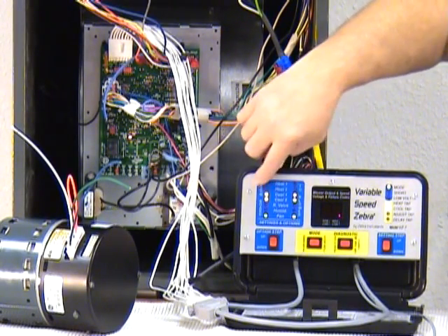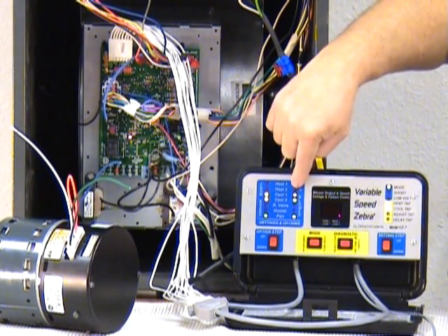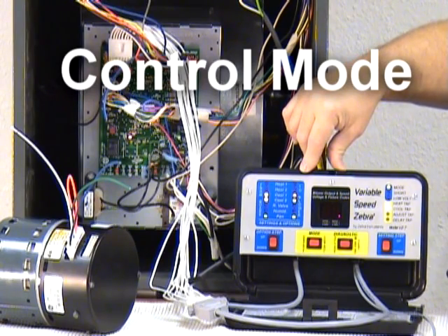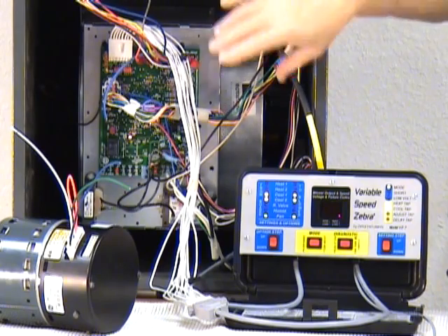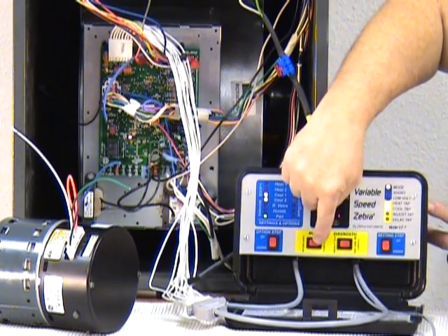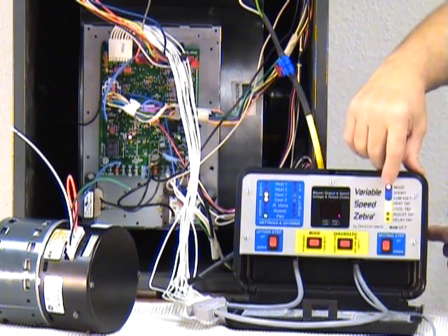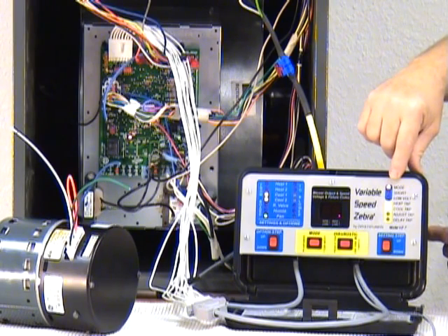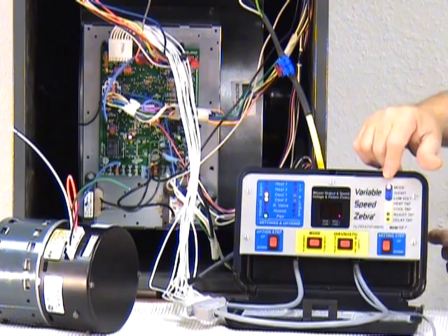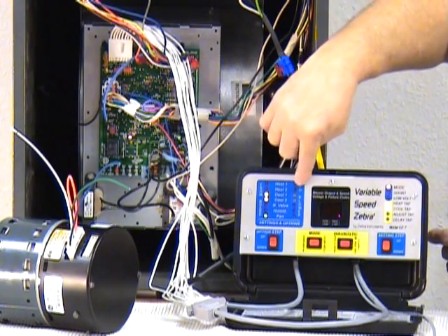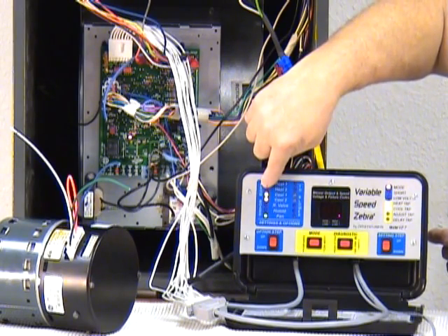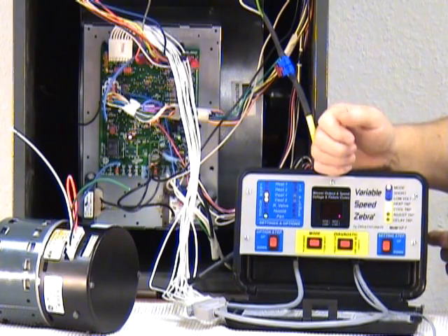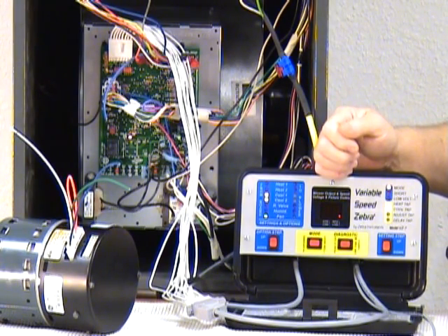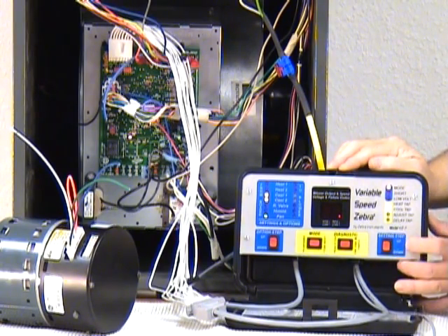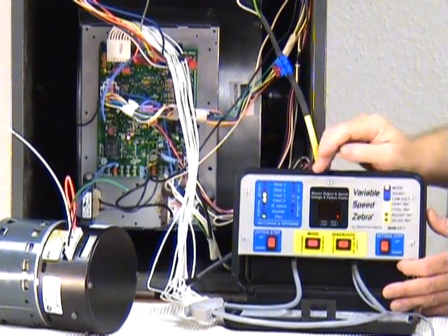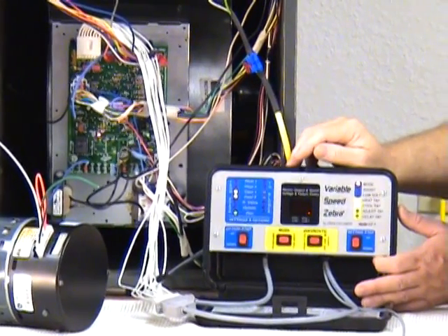We're watching and observing signals coming from your board as they're passed along to the motor. Another way of diagnosing problems in a system, instead of changing your thermostat or using your ZebraStat to change the settings on your board, is to go into control mode, by pressing the switch and releasing it. In control mode, your mode light will turn red. It's hard to see from the video, but it actually is red. And your signals will stop going out to the blower. In other words, you can see the signals coming in from the board, but they have absolutely no effect in control mode. In control mode, you control what you want your motor to do. You'll use your setting step switch, up or down, and your option step switch to select what signals you want to send out to that motor.